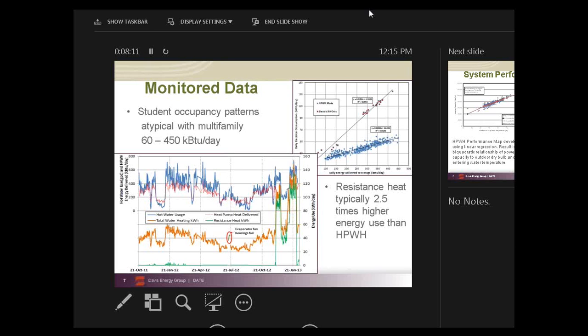In the tail end of monitoring, you can see where the heat pump water heater had shut off due to its lost set points. And it took some time for the building maintenance staff to respond because it was during the Christmas break, and when the sessions resumed again in January, other maintenance items took a little higher priority. In the second chart, you can see the difference in energy consumption is related to the demand for both electric resistance operation periods and the heat pump water heater operating periods. There's almost 2.5 times the amount of energy used when we defaulted to electric resistance as compared with the heat pump.